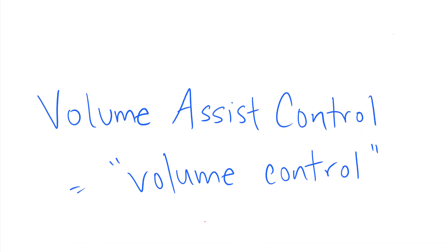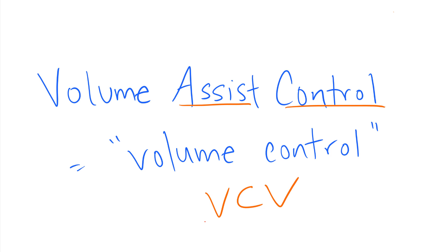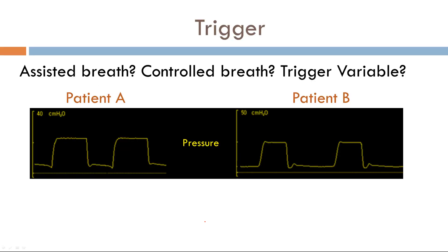The same goes for volume assist control ventilation, or volume control (VCV). A lot of information is in the name: volume assist control ventilation has both assisted breaths and controlled breaths. The trigger variables are either pressure or flow for assisted breaths, and time for controlled breaths.